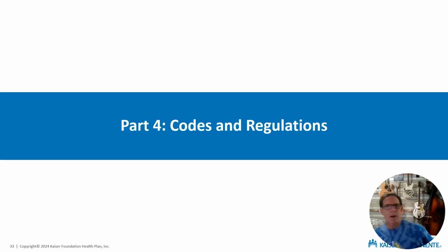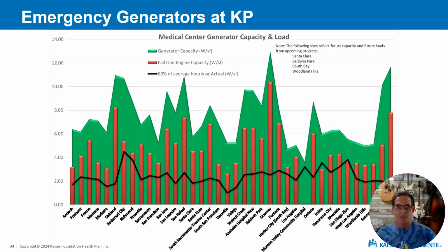So let's talk a little more about codes and standards in the regulatory environment, since we're kind of on the topic. And we'll start with emergency generators. So supposedly at Kaiser, we size our emergency generators based on the code. Code only requires that critical and life safety branch, but it requires generator sizing based on connected loads.